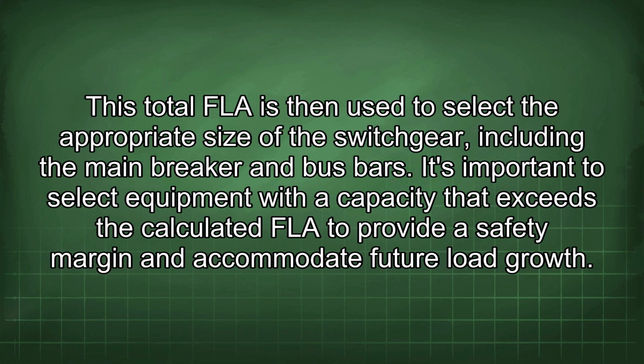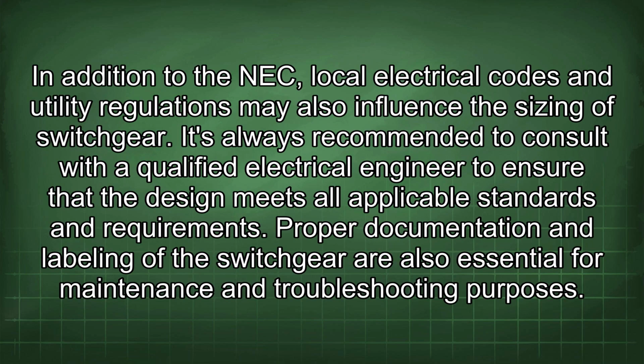This total FLA is then used to select the appropriate size of the switchgear, including the main breaker and bus bars. It's important to select equipment with a capacity that exceeds the calculated FLA to provide a safety margin and accommodate future load growth. In addition to the NEC, local electrical codes and utility regulations may also influence the sizing of switchgear. It's always recommended to consult with a qualified electrical engineer to ensure that the design meets all applicable standards and requirements. Proper documentation and labeling of the switchgear are also essential for maintenance and troubleshooting purposes.